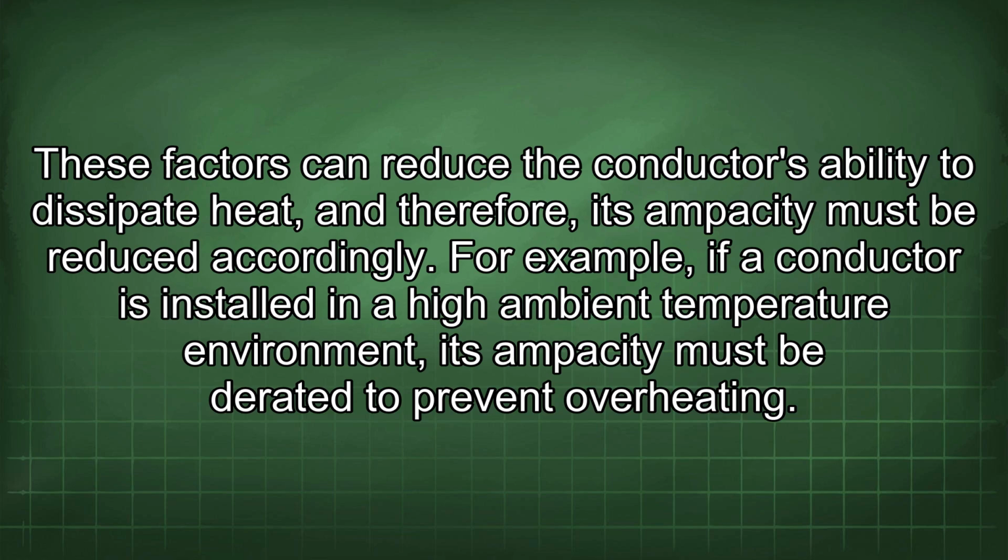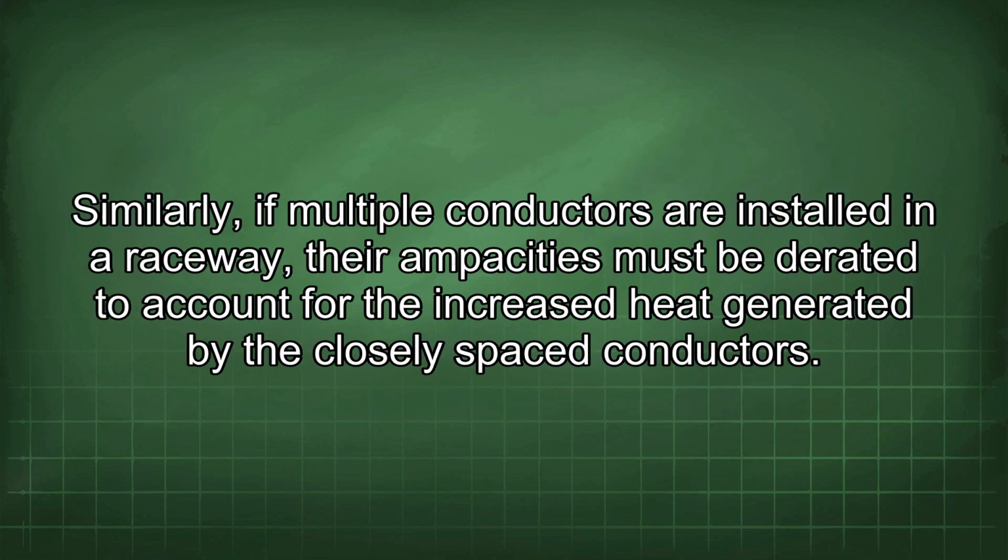For example, if a conductor is installed in a high ambient temperature environment, its ampacity must be derated to prevent overheating. Similarly, if multiple conductors are installed in a raceway, their ampacities must be derated to account for the increased heat generated by the closely spaced conductors.